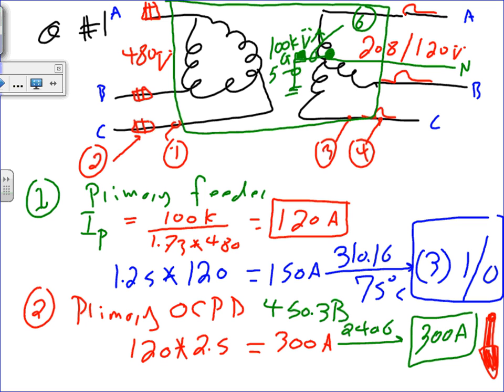Oh, why? Because I created a neutral. Do you have any neutral on this side? You created a new neutral. Every time you create a new neutral, it's a separately derived system. Every time you create a new, meaning you go delta-Y. If you go Y-Y, which we rarely do, and you tie the neutral of the primary with the neutral of the secondary, it becomes a non-separately derived system. It's a separately derived system because you created a neutral. Show me where the neutral is here. Do you see any neutral here? There's no neutral. I created a new neutral. That's a separately derived system.